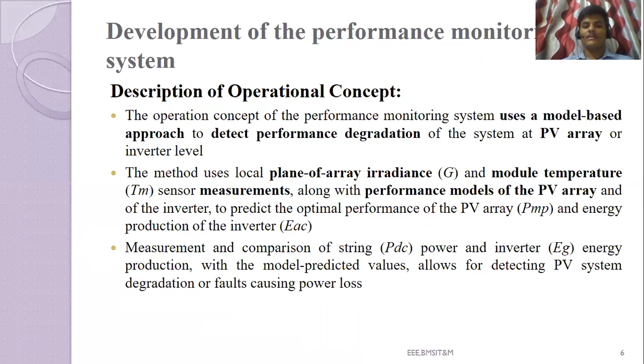Measurement and comparison of string power and inverter energy production with the model predicted values allows for detection of PV degradation or faults causing power losses. While we measure all these parameters, we get to know the fault causing parameters and the degrading capacity of the inverter.